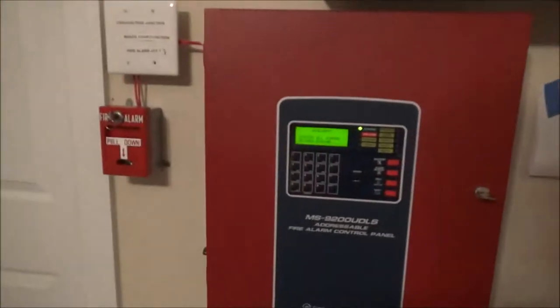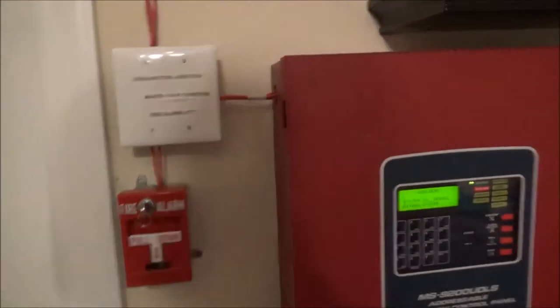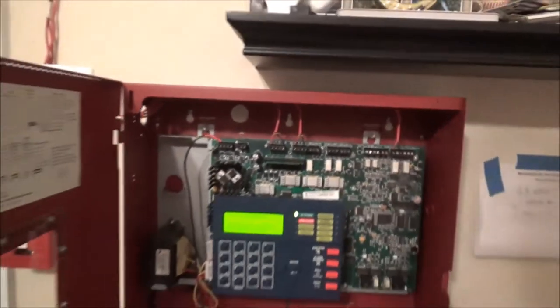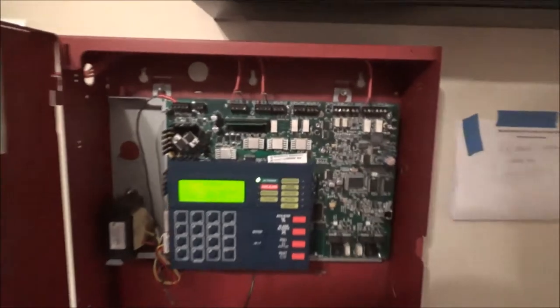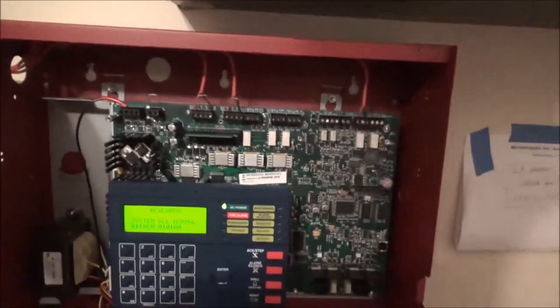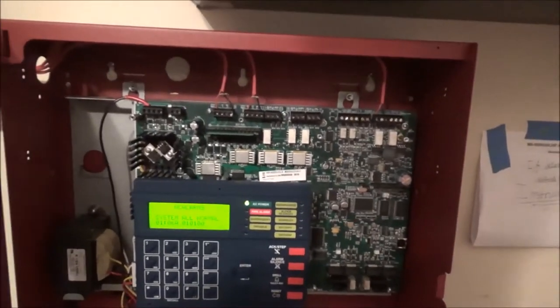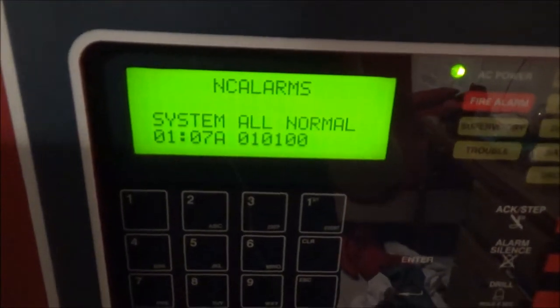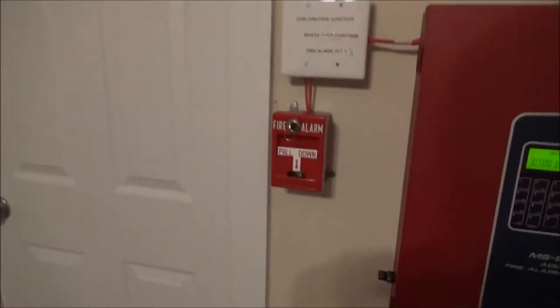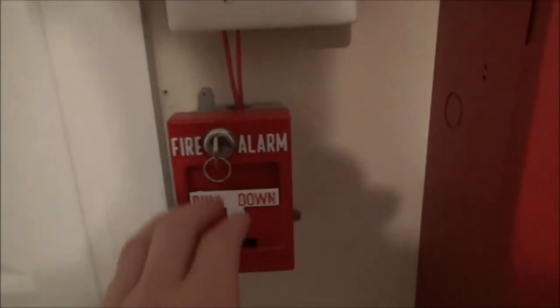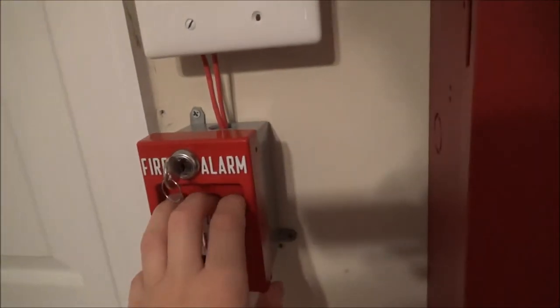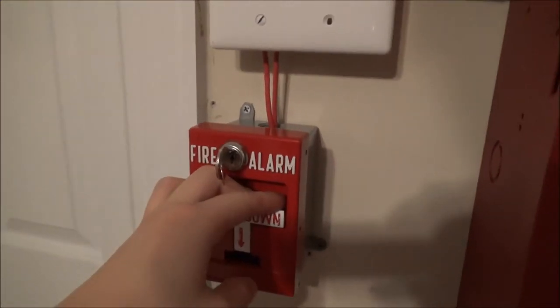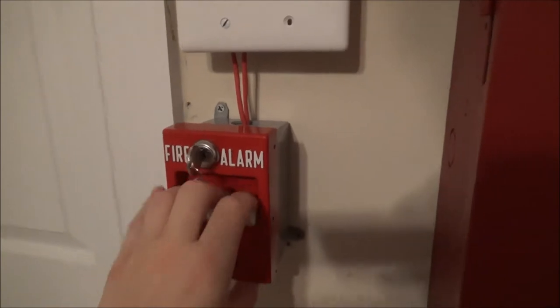So there is the system. By the way, something I forgot to mention in the last system test - look at the wiring inside the panel right now. Is that not some neat wiring? Like that's a neat wiring job. I know there's not very many wires so it's kind of hard to screw it up, but you know what? I'm very happy with this wiring. NC alarm system all normal. Both of these are set to March time, so we'll start with the pull station since we did the detector first last time. Here we go, three two one.